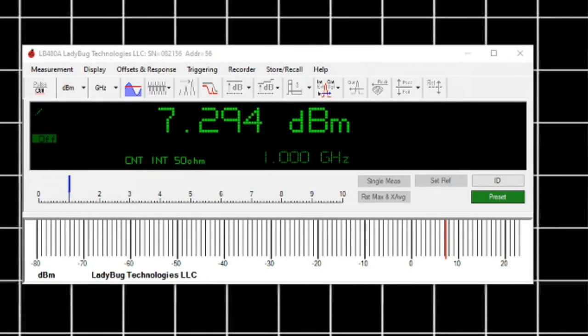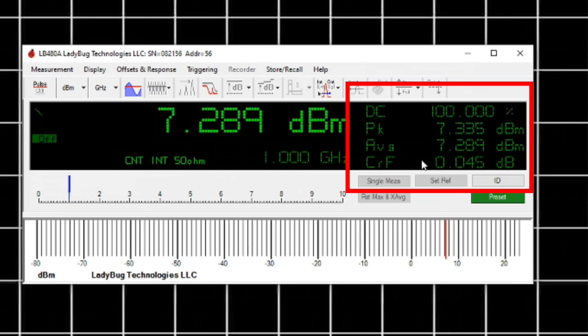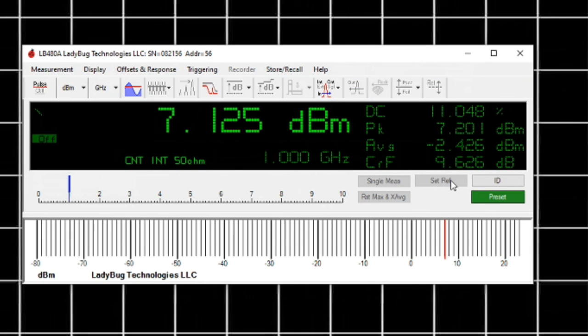This is the power meter for our pulse sensors. It measures average power until it's placed in pulse mode by clicking this button. Once in pulse mode, the peak power, pulse power, duty cycle, and crest factor, and average power are displayed. When I change my signal from CW to pulse, you notice the duty cycle changes and the average power changes. The peak and pulse power remain the same because there's very little overshoot or droop on my signal. Remember, this is a non-triggered pulse measurement.